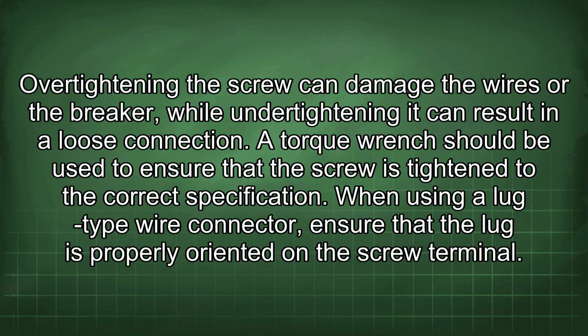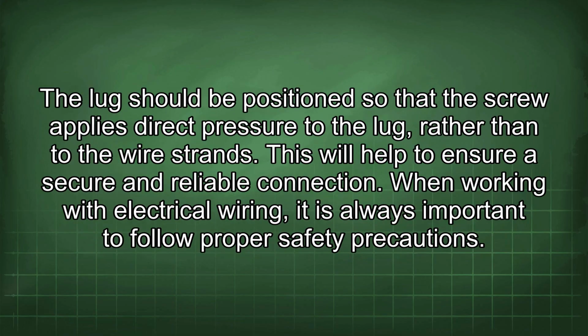Over-tightening the screw can damage the wires or the breaker, while under-tightening it can result in a loose connection. A torque wrench should be used to ensure that the screw is tightened to the correct specification. When using a lug-type wire connector, ensure that the lug is properly oriented on the screw terminal. A lug should be positioned so that the screw applies direct pressure to the lug, rather than to the wire strands. This will help to ensure a secure and reliable connection.